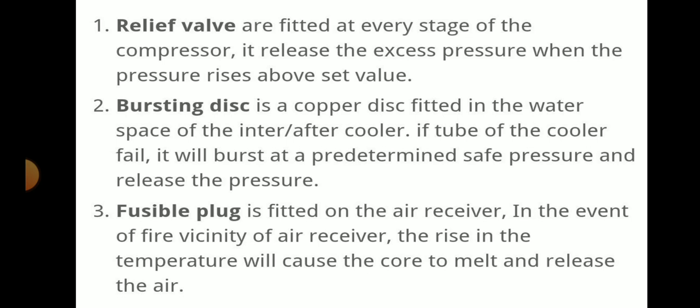Relief valves are fitted at every stage of the compressor, and release excess pressure when the pressure rises above the set value. So it is a safety. The bursting disc is a copper disc fitted in the water space of the intercooler and aftercooler. If the tube of the cooler fails, it will burst at a predetermined safe pressure and release the pressure. The fusible plug is fitted on the air receiver. In the event of fire in the vicinity of the air receiver, the rise in temperature will cause the core to melt and release the air.